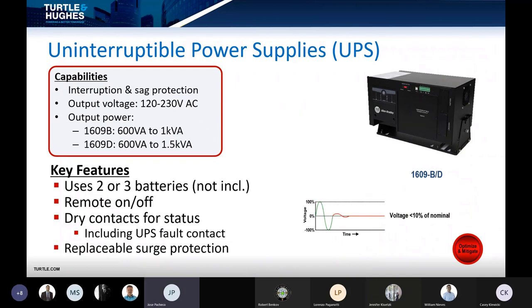The uninterruptible power supply is designed to ride through prolonged interruptions and manage controlled shutdowns. The goal is to avoid unwanted and costly system crashes. It's designed to more effectively integrate into a control system than a commercial UPS. Key features include expandable and hot-swappable battery options, remote on and off capabilities, dry contacts for status, and replaceable surge protection.